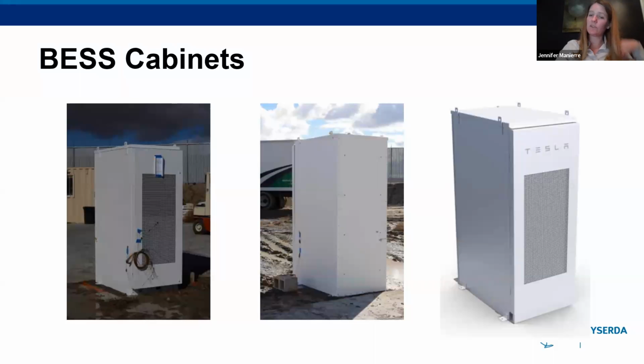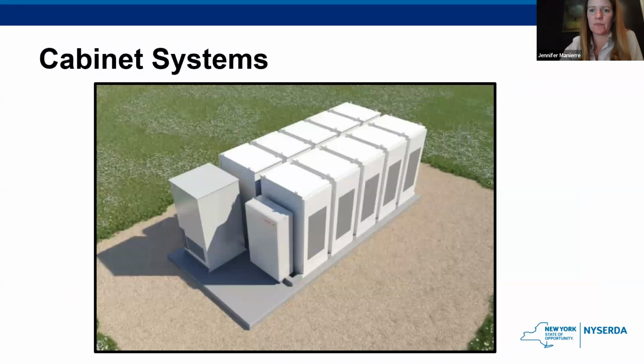So an example of what we refer to as cabinets, also filled with batteries, just a little bit smaller, and typically seen installed outdoors. This is a cabinet system, and it's also a good example of that size and separation requirement not applying when the system is considered remote. This must be a remote system, right? It has nothing really around it, so you can have those individual units closer together. They definitely don't look like they're separated by 3 feet.